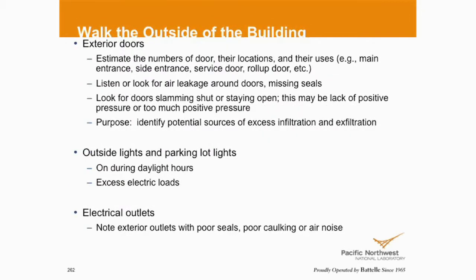Doors, again, how many doors do we have? Are they sealed up properly? Can you see light underneath the doors? In the middle, if it's double doors. Check whether the building is positive or negative at your outside doors. How do we check whether the doors are positive or negative? Yeah, Marta knows. We pull out our $1 test tool. If you got a $20 test tool, toilet paper, something, tissue paper, whatever, and check. We actually checked last night one of the buildings. It was nice and positive, so that was good to see. So that meant that Towson is doing something good.